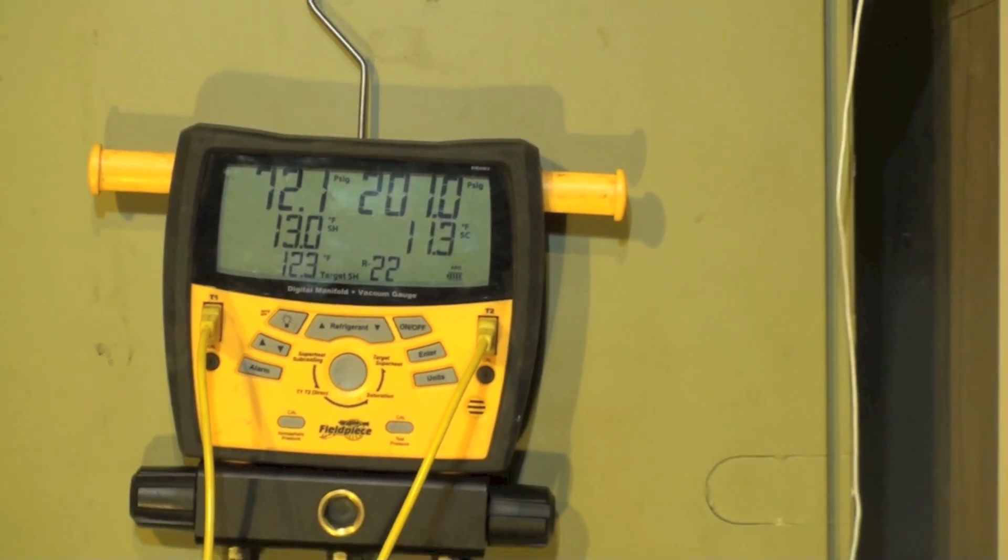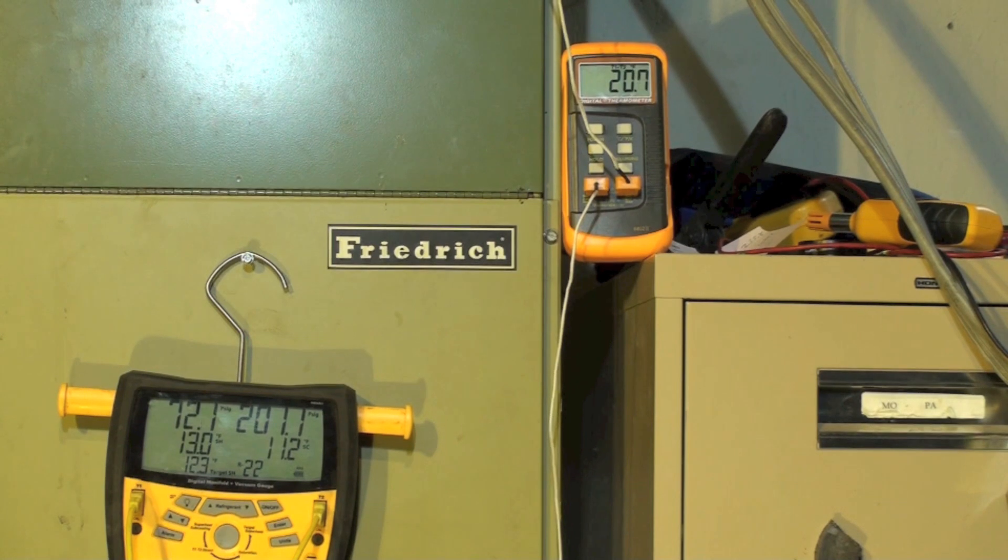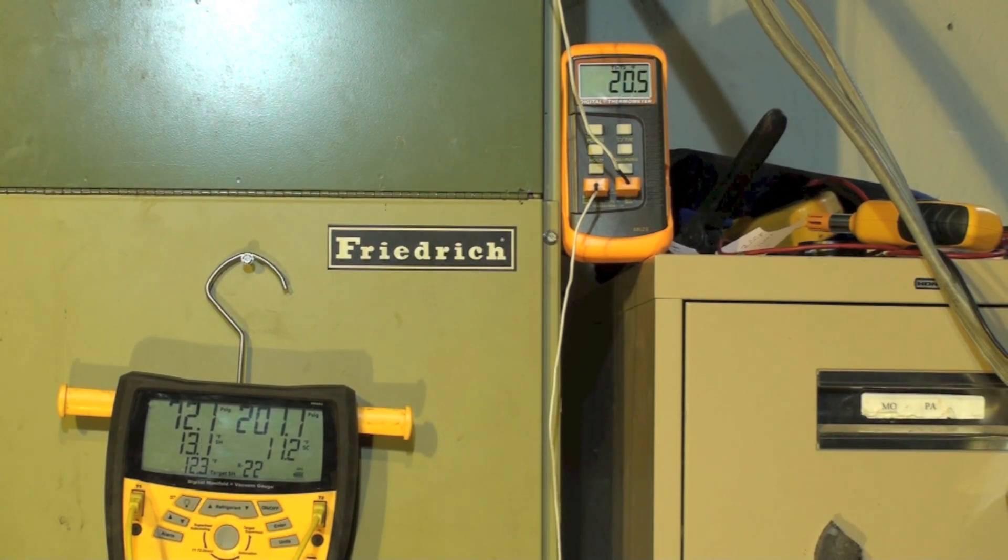Let's also look at the temperature across the coil. Our temperature across the coil is 20.8 or 20.5, whichever. Anyway, that's about where it should be. And so the unit was low on charge, that was the problem.